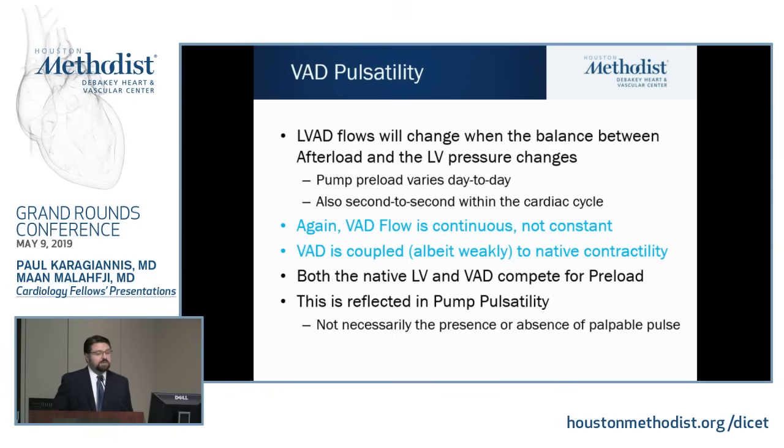The important thing is also that LVAD flows change second to second in accordance with the cardiac cycle. Small differences in pressure cause a reliable waveform change, a reliable change in the VAD flow that I'll show in a second. But this is another interesting concept.